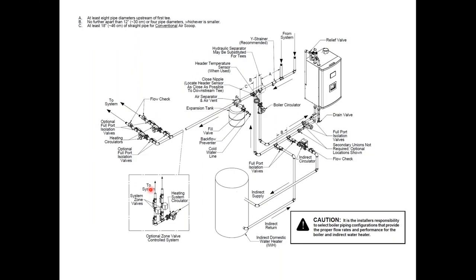This is showing standard piping of the product with an indirect water heater. The indirect can be either piped inside the boiler loop, as this one is, or it can be added as a second zone for the system. We would just have to, in the pump selection, turn the boiler pump off to allow the units to run.